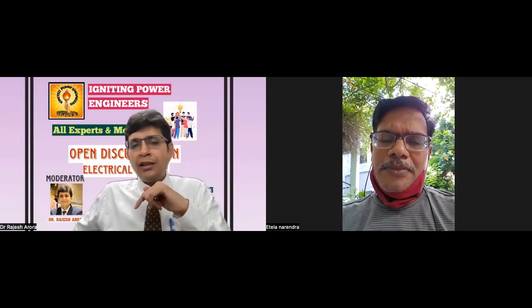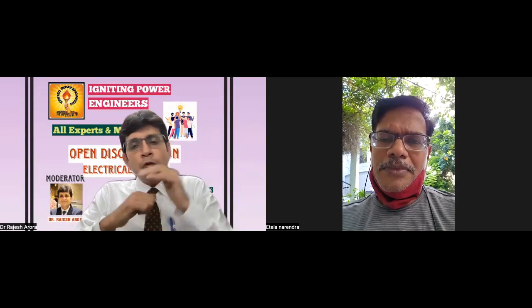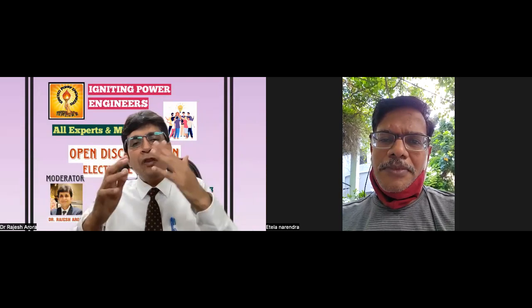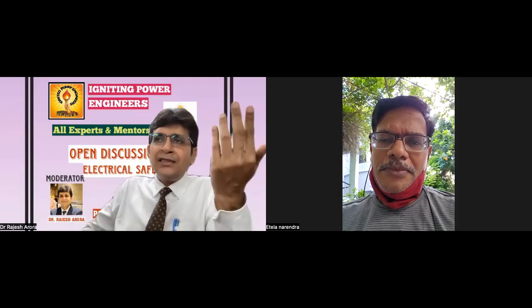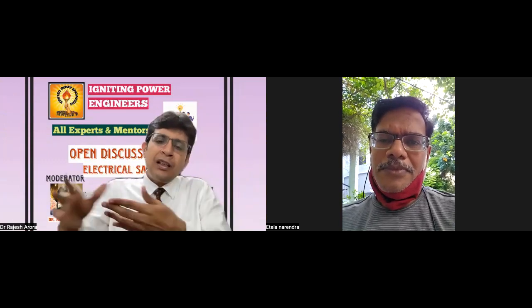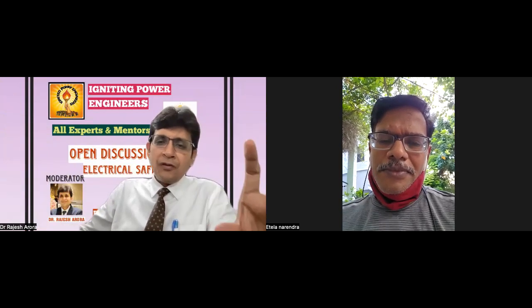At the time of a single phase to ground fault, that is called the SLG fault, the voltage of the healthy phases becomes high. It is not 220 volt; it becomes equal to the line voltage of a 3-phase system, which means it is around 415 volt. All the gadgets connected in the houses in the building will burn out because they can withstand 270 volt at most. When they receive more than 400 volt, they will definitely be damaged. This is the reason for that overvoltage because of the floating neutral.